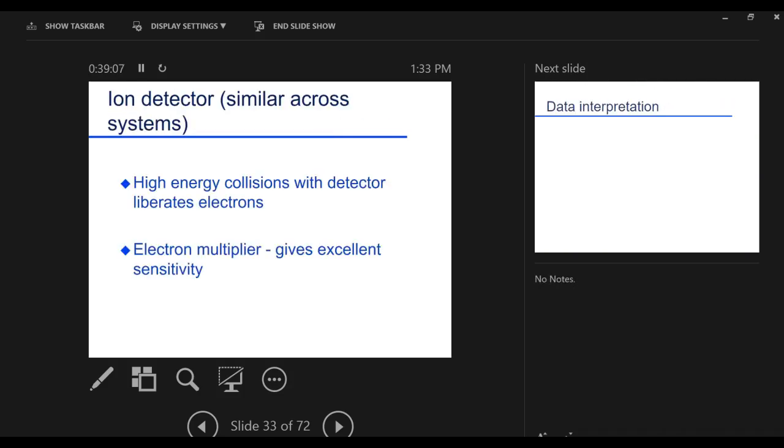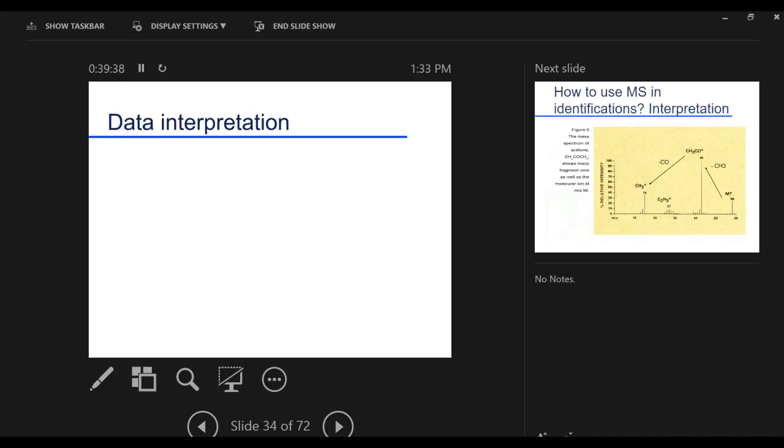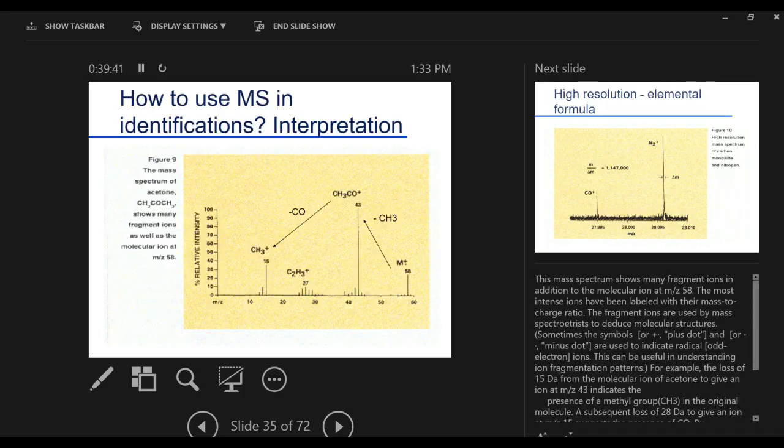Oh, well, okay, I guess I don't have a picture of that. It gets focused on another plate, so those 10 get converted into 100. The 100 get into 1,000, and so I'm just multiplying the electrical charge, so I've got something to measure. So it's an extremely sensitive detector. That's basically what gives mass spectrometry its sensitivity. We're detecting charged particles. The charged particle hits a charged plate, it gives up some multiplication of signal. It's really a fascinating piece of equipment when all is said and done.